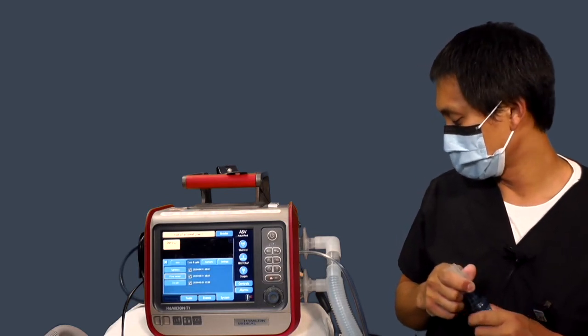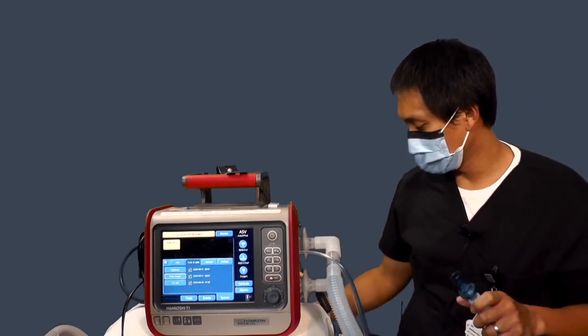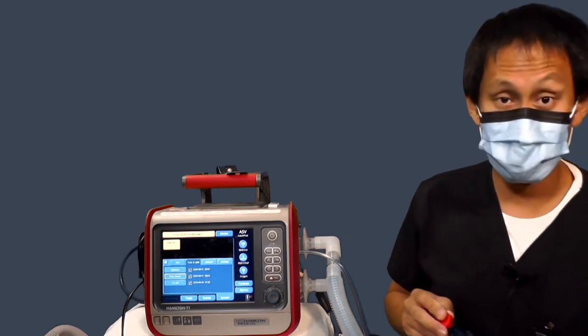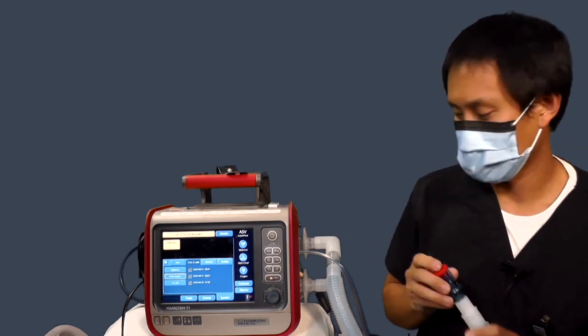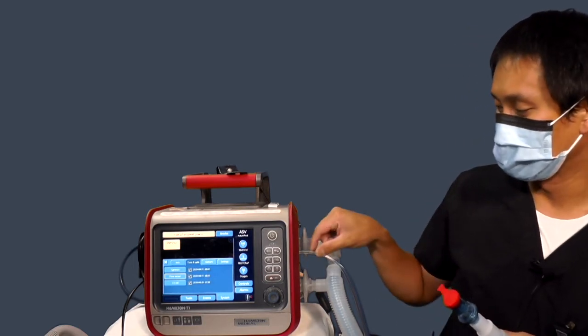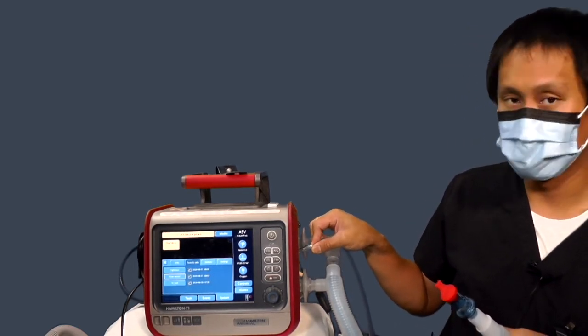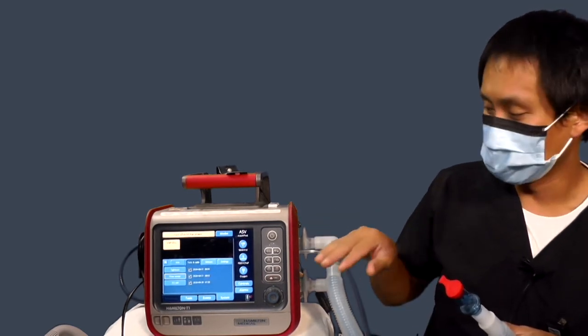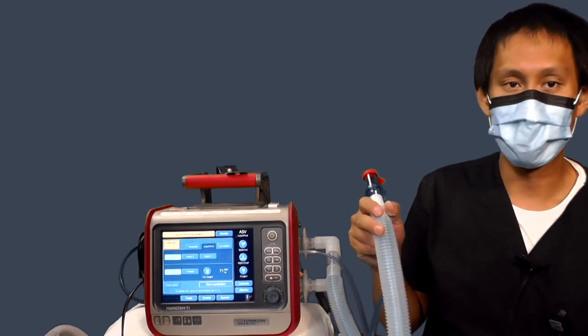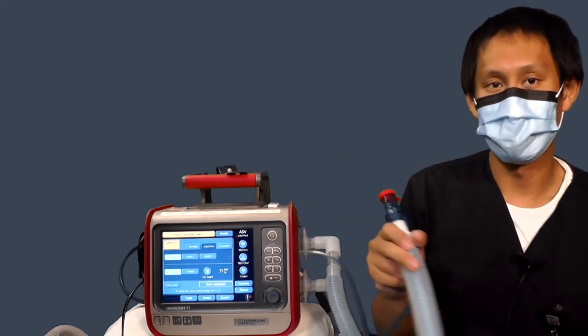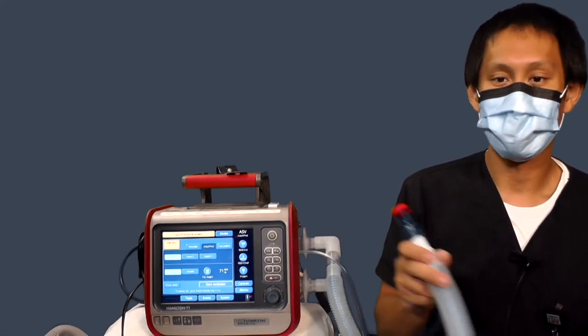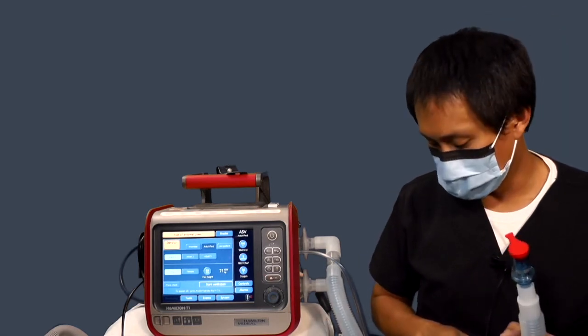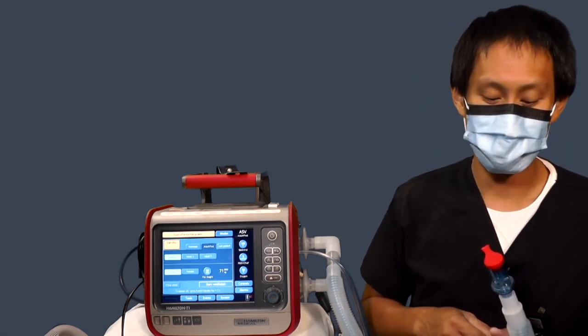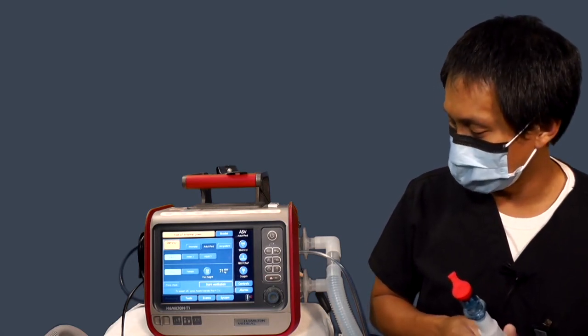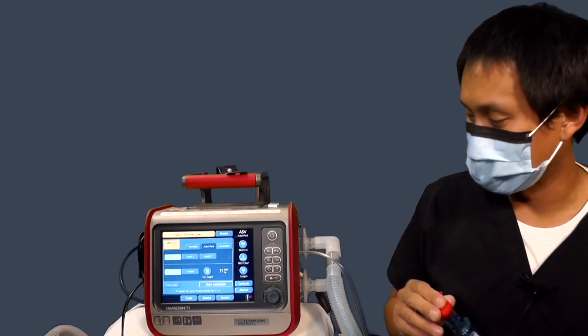In my experience, the test that usually fails for people is the flow sensor test, and that's usually user error. It's usually because they don't have the tubes connected tightly to the ventilator, or they didn't follow the prompts closely enough, or as they're doing the calibration, they're walking around or shaking the tube, adding some extra flow into the circuit, and that's causing them to fail. So try to hold the circuit still while you're doing the flow sensor test, and you should be able to pass this almost all the time.